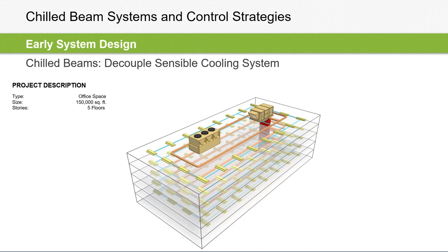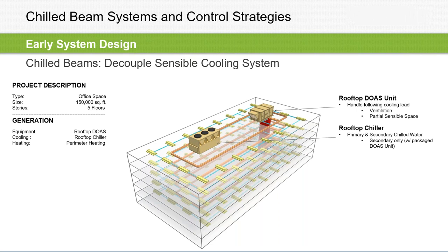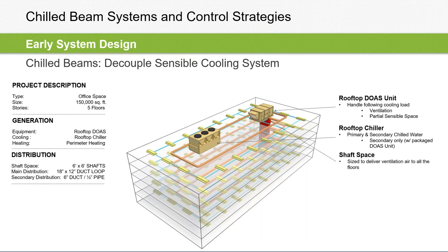But I would say 60% is a pretty conservative reduction in airflow from a VAV baseline system to a chilled beam system. And we do have a bigger chiller most likely, and some more pump energy is going to come back into the space. But it cleans up the footprint of the building a little bit by reducing that ductwork and mechanical room size.